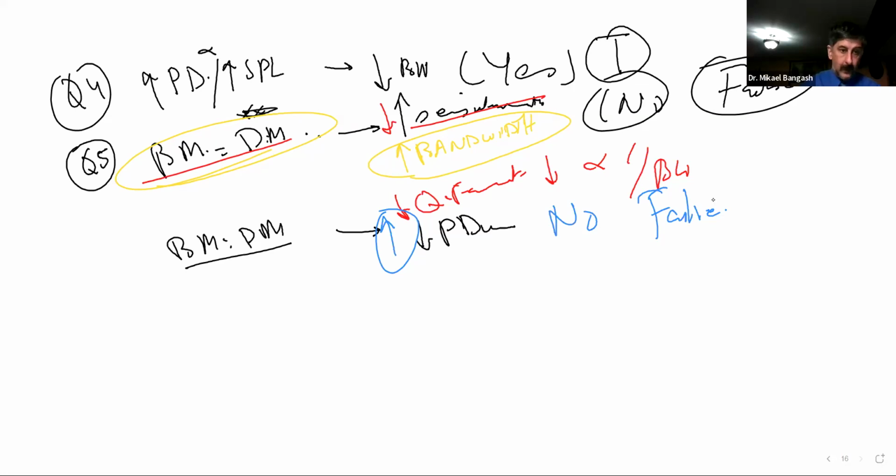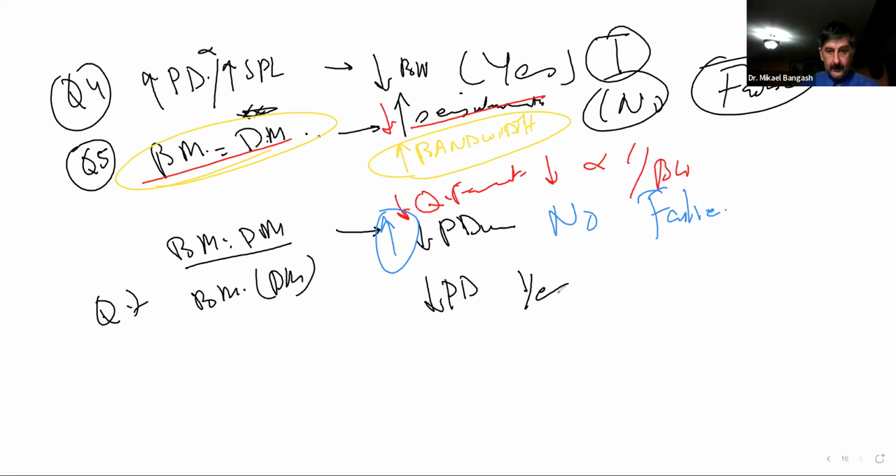Likewise, in question 7, it's the same. Where again it says, using damping material in a transducer, does that decrease the pulse duration? The answer to that is yes. And since the answer is yes, that becomes true.